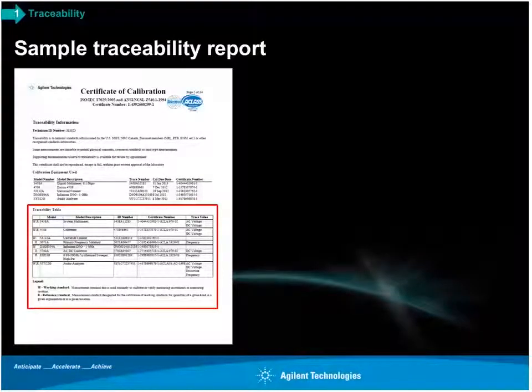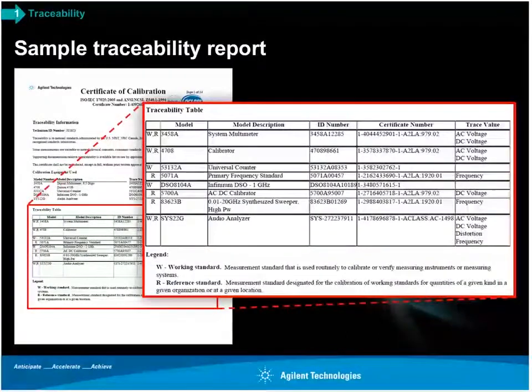All right, now whenever you get a calibration from an outside lab, you get a certificate of calibration. Hopefully you also receive measurements, but the one thing that you almost always, well, I've never seen a case where they didn't, you will receive is this calibration report. As you look a little more closely, I'm expanding it here, what you can see is a list of models, what the instrument was, an ID, and a certificate number for it, which if you investigate that further will allow you to investigate specifically the traceability path. That could be traced all the way back to some primary standard.